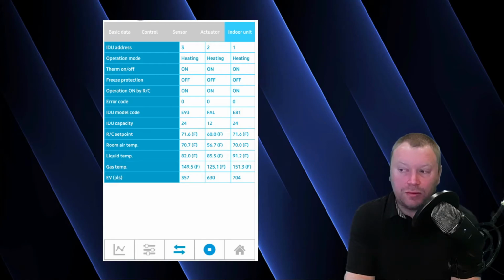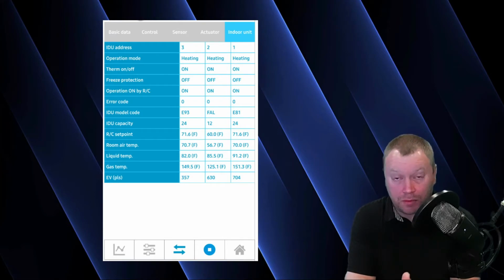And then if we look at unit number 1, we have a 71.6 degree set point and a 70-degree room temperature. So again, we're approaching that set point. I expect in the next couple of snapshots, the expansion valve position on unit number 1 to start closing down. Because as we get closer and closer to set point, we don't want to overshoot. We want to get as close to the set point as possible without overshooting. So if we were to base everything on this one snapshot, keep in mind, this snapshot is going to change constantly.